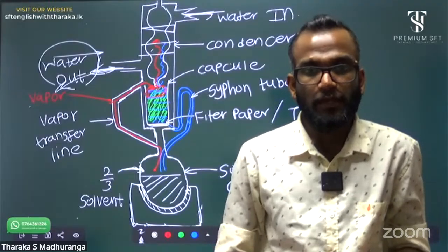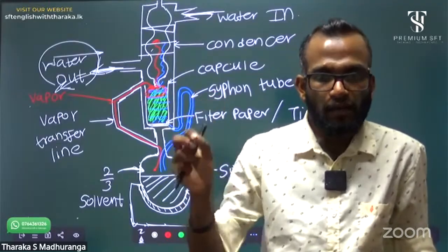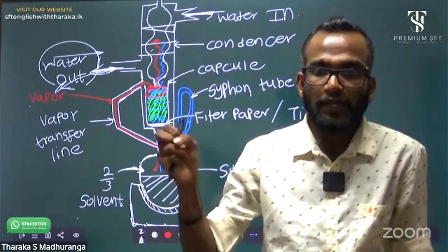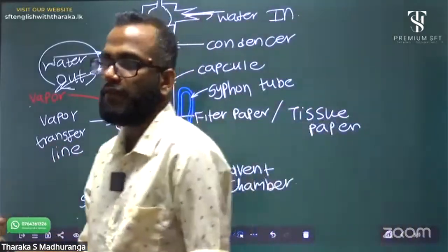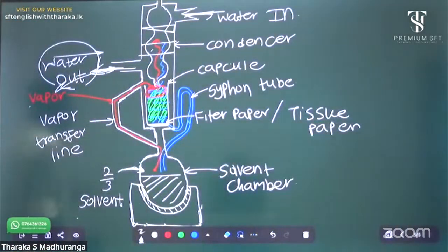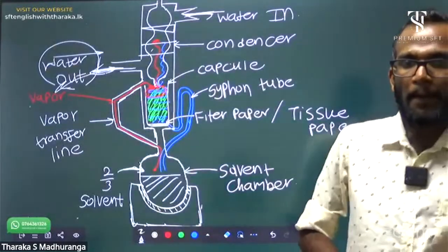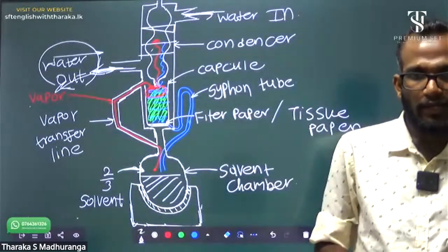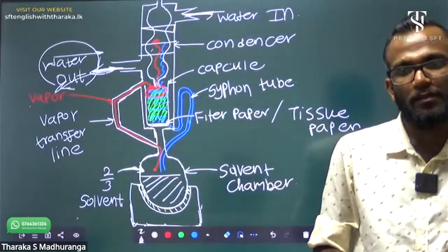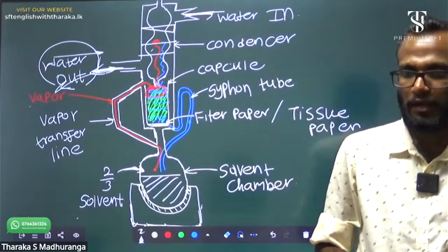Therefore, your answer should be: to make sure the condenser is always completely filled with water. Tanya, you are correct, but your answer should be updated like this. Understood?